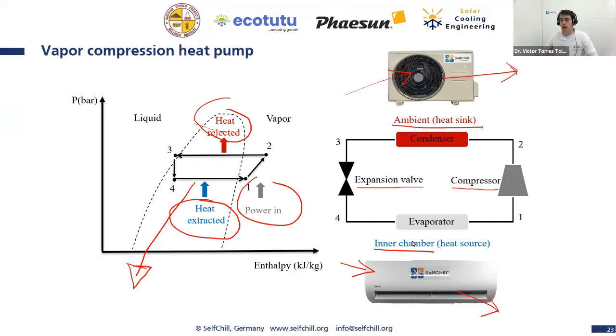Then we have the expansion valve, and if we have an evaporator, that is actually a heat exchanger, you expand the liquid, and then you are able to go from liquid to gas, to evaporate the refrigerant and be at a stable temperature, let's say 10 degrees, it could be 0 degrees, depending on the system. Then you are also able to release a lot of cooling energy into your room, into your device. Yeah, and that's why we use a refrigerant. That's why we condense and evaporate, because we want to have a density of energy. But that's all. A condenser and evaporator is just a heat exchanger. It is no more than that.